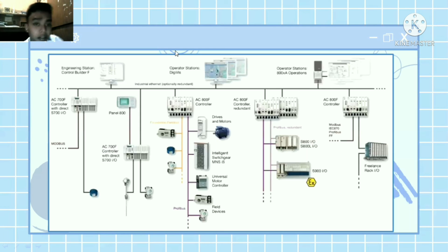The last, number 5, is smart or intelligent devices. Intelligent field devices and field bus technology are advanced features of DCS that replace traditional input/output subsystems. These smart devices bring the intelligence required for simple sensing and control directly into the primary sensing and actuating device, reducing the need for the DCS controller to perform routine sensing and control processes.